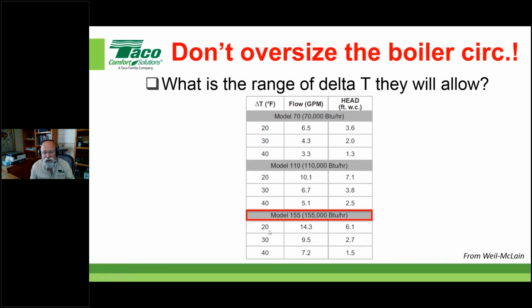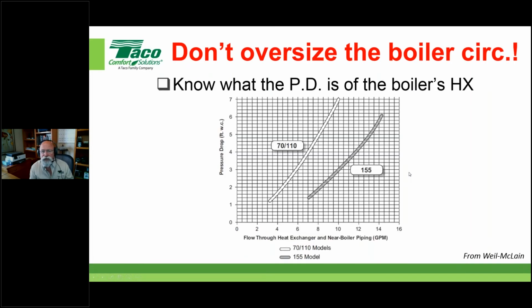right? So in this case, they're showing you a 20 degree, a 30 degree, and a 40 degree delta T, and they're giving you the following information based on that: what to expect for flow, your initial thing you need for sizing a pump, and then what to expect on the pressure drop through the near boiler piping and the heat exchanger in this case. So I'm going to show you what that looks like. These are the charts we're talking about. This is what you need to be able to comprehend and understand and how to interpret this, okay?